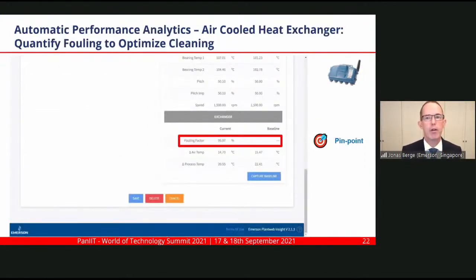And lastly, another example, air-cooled heat exchanger - I think you get it - additional sensors and the software. If you have an air-cooled heat exchanger, or fin fan as it's called, with multiple cells, it pinpoints which cell is fouling and needs cleaning up.